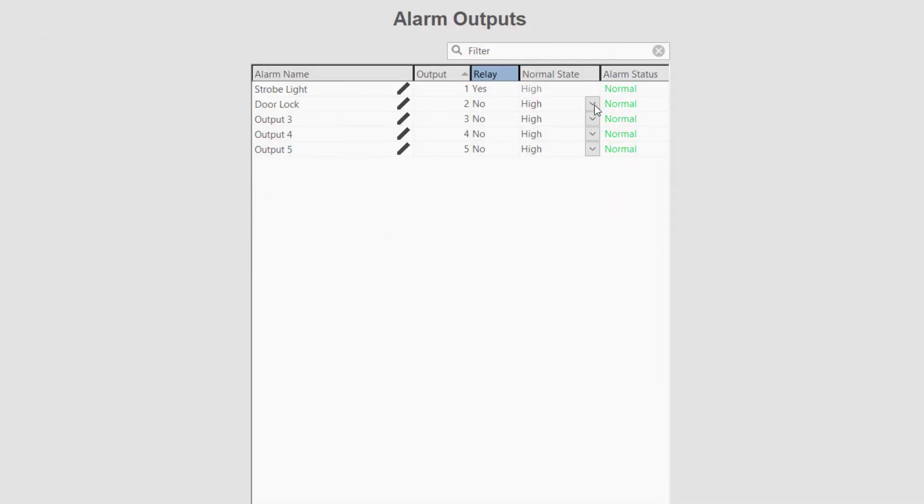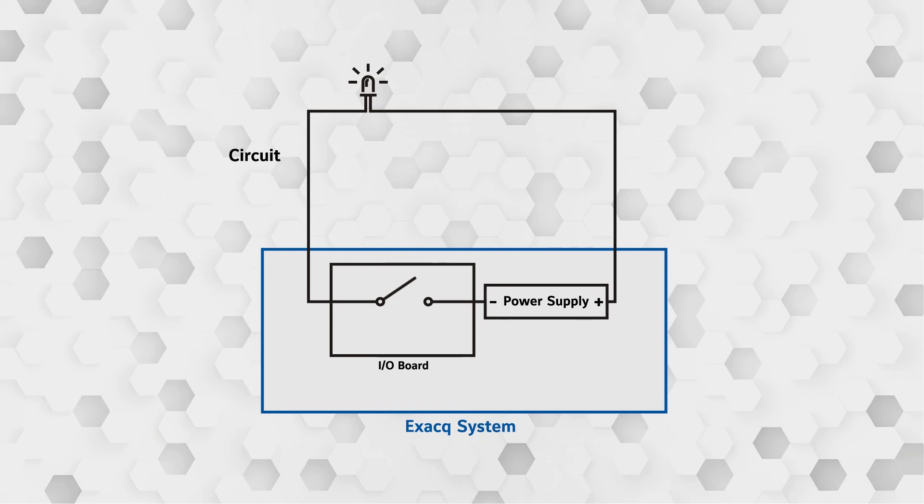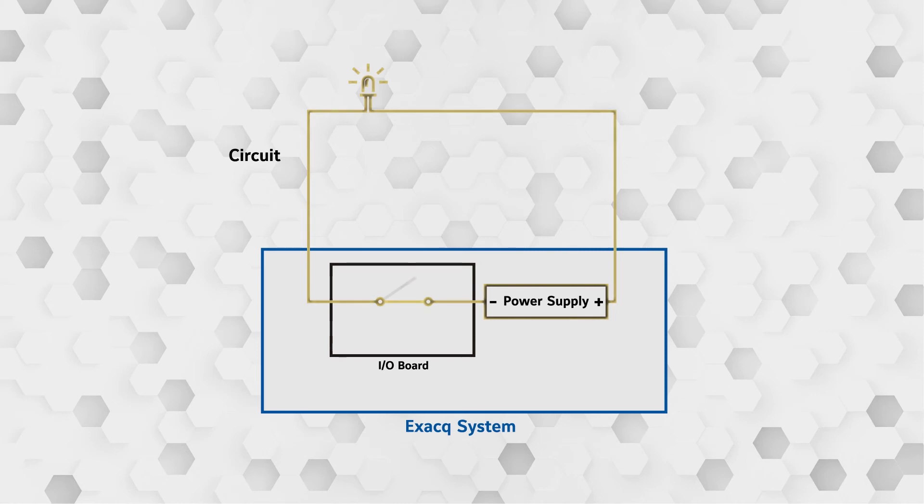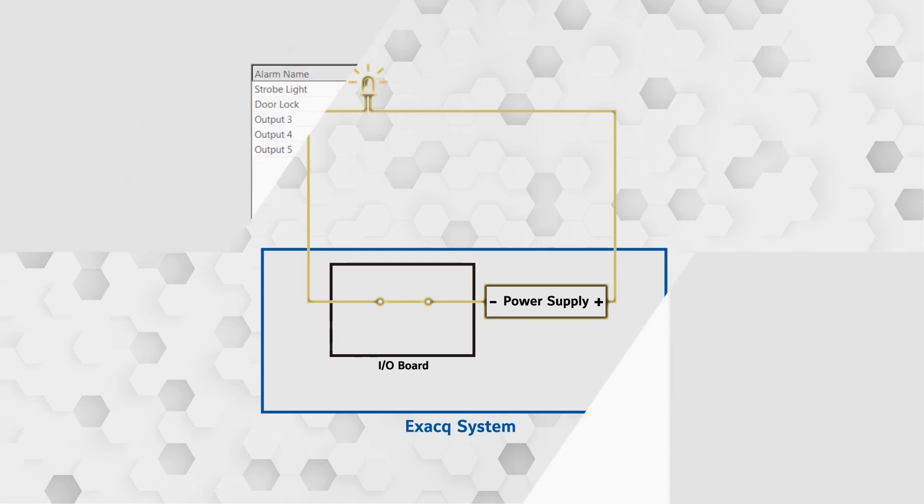For non-relay alarm outputs, you should not apply external power. These are powered TTL circuits providing 5 volts at no more than 50 milliamps of current intended to be connected to the input of external devices. They may also be used to trigger user-provided external relays capable of controlling much greater current.